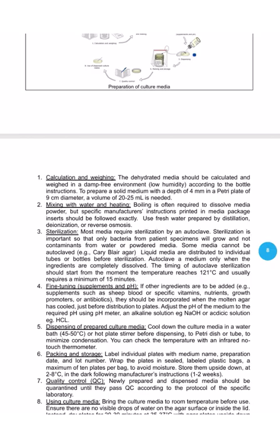So once you want to sterilize it, you use what we call an autoclave. An autoclave is similar to the pressure cooker, but this is specific for the microbiology laboratory. So you put your medium there, and then you have to make sure that this medium could be sterilized using the autoclave, because there are certain types of medium you should not sterilize using an autoclave.